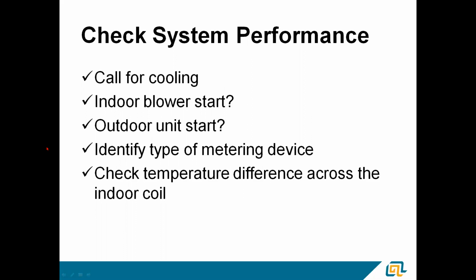It's a good time to try and identify the type of metering device. Anything installed in the last 12 to 15 years should have a TXV for a metering device. However, I know that restrictors are starting to make a comeback. Seeing a few more and more of them. So just be sure what you're working on. If it's a system you've installed, you pretty much know what your company uses, so there's not a lot of digging. You know that it's probably a TXV. And of course, check the temperature difference across the coil. See if it lines up and it's in the range that it should be.